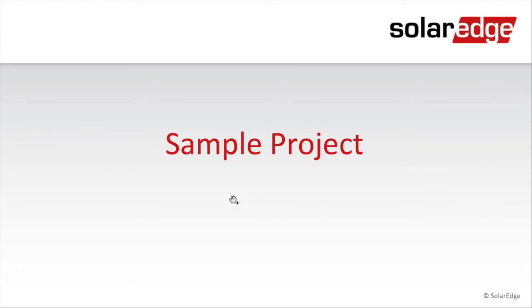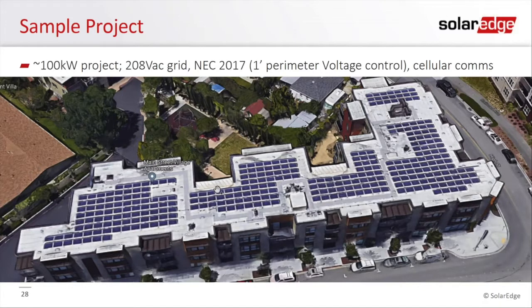So now that we've gone through some of the advantages of the SolarEdge solution, as well as more detail on the Synergy 43.2 kilowatt inverter, here we're going to look at a sample project. This sample project is a typical 208 application, an apartment building, with a pretty cut up roof. There's actually 5 distinct parts of the array here. We're going to assume, of course, a 208 grid connection. We'll also assume NEC 2017, so 1-foot perimeter voltage control. And we're also going to assume that the communication method will be a cell card or cell modem.